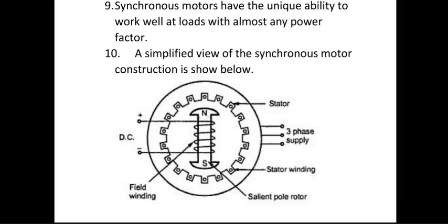Another thing is that rotor poles can be either mechanically built, that means you will be able to see poles physically, or for high speed, you may go for realizing the poles electromagnetically, because for high speed rotors, mechanical construction is not very desirable. The poles start coming off as speed is high.